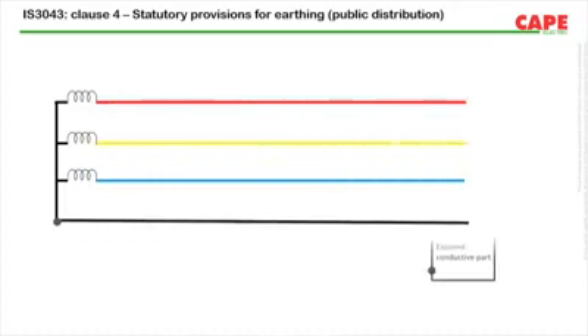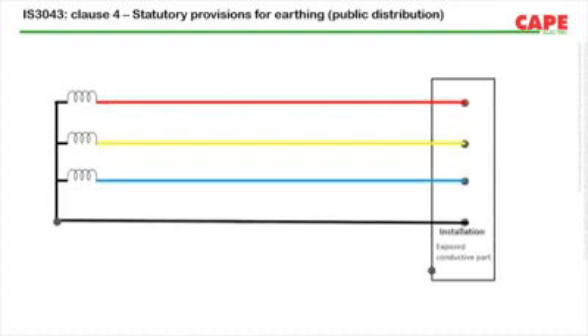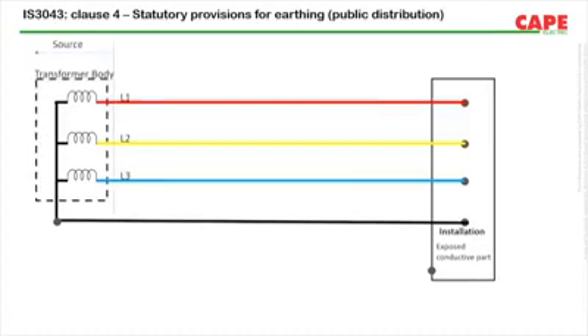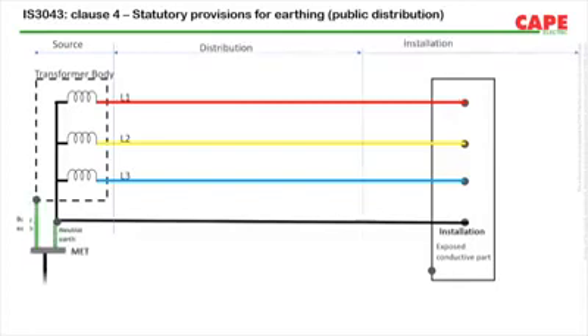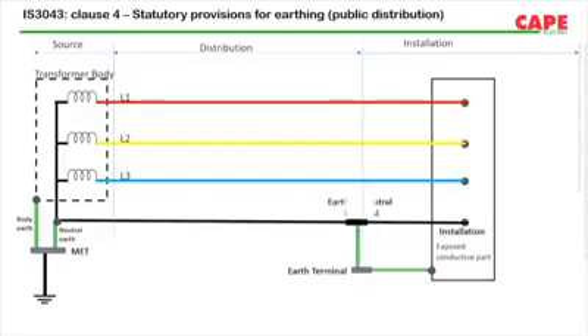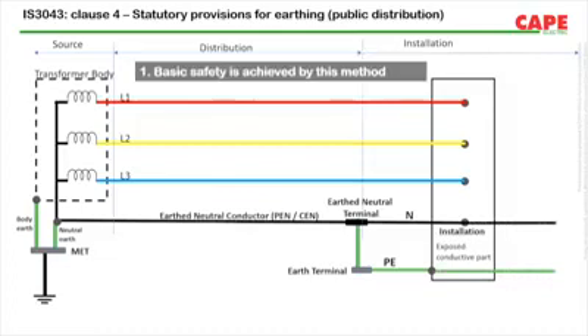Clause 4 of the new IS 3043 improved the statutory requirement of earthing applicable for public electricity distribution. A clear and improved explanation of TNCS system with the PME is provided in this clause. In the basic TNCS with PME network, the meaning of earthed neutral terminal and earthed neutral conductor can be noted from this picture.